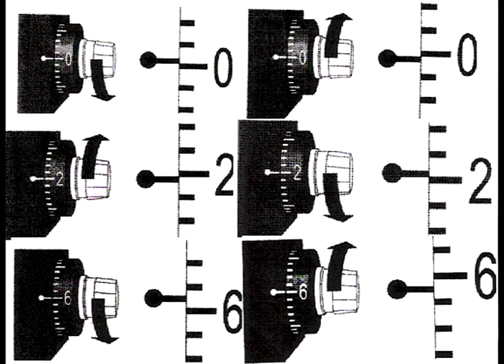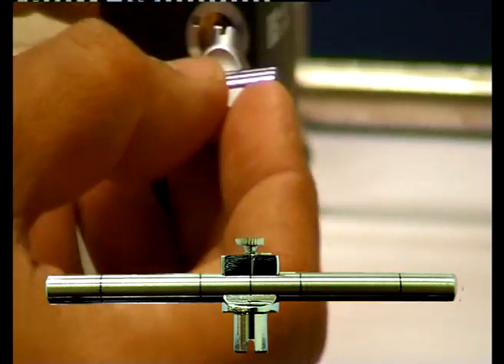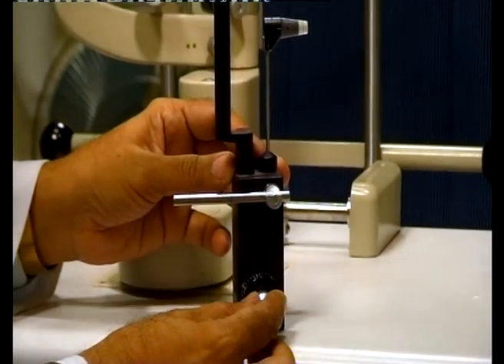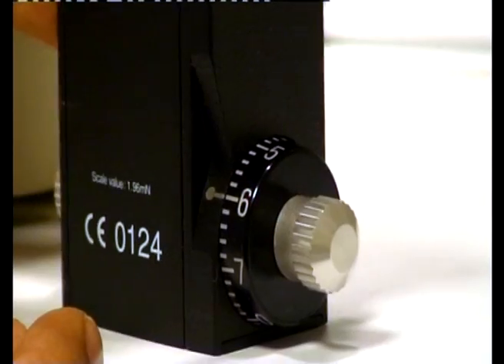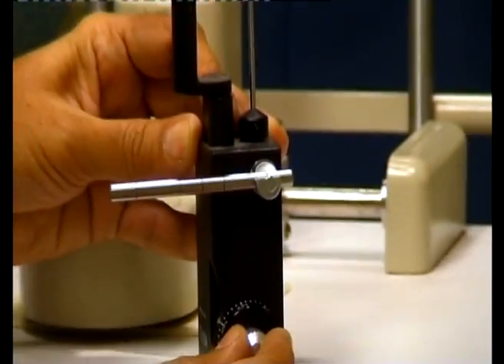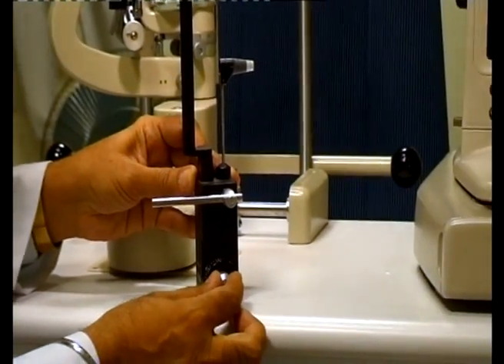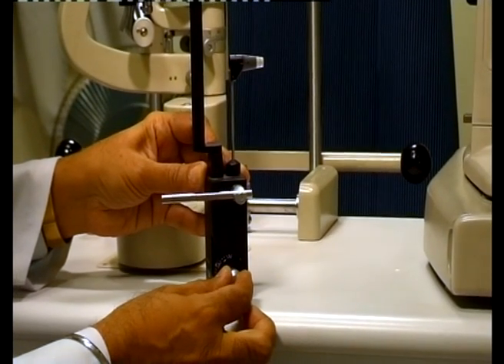Calibration of the instrument should be done once a month. The calibration check is performed at scale readings of 0, 2, and 6. Precise setting of the mark is the key to successful calibration check. The procedure of calibration should be carefully understood by going through the manufacturer's instructions in the manual. If any defect is detected, the instrument needs to be sent to the manufacturer for repair.